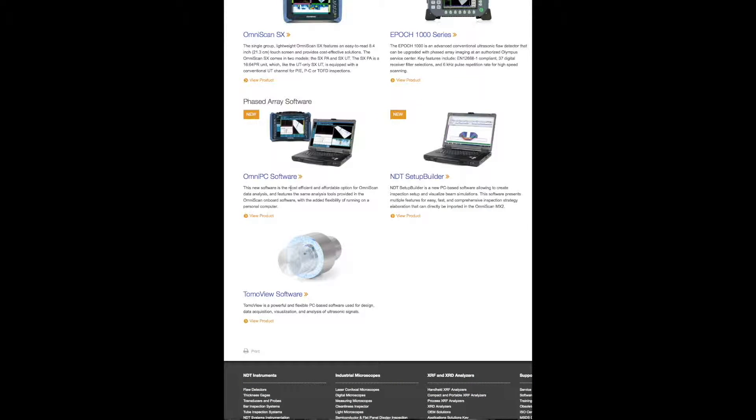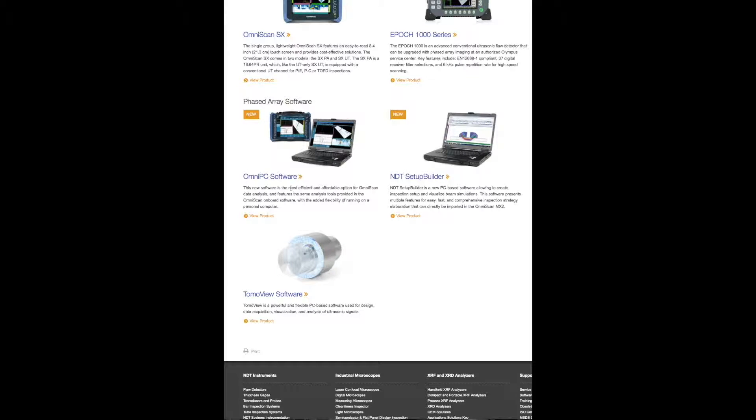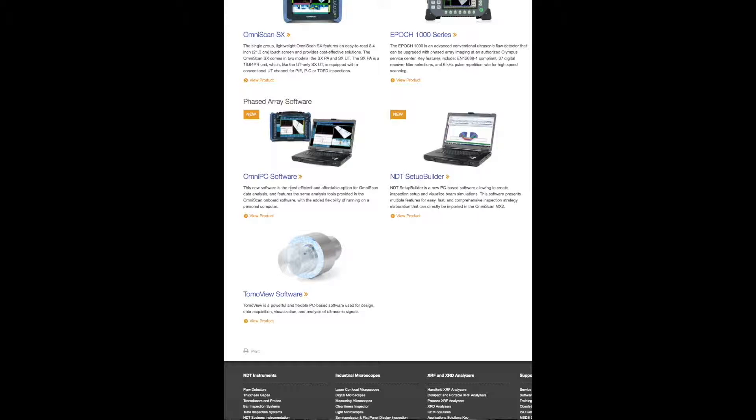Some of the software that Olympus has are Omni PC, NDT Setup Builder, and TomoView. Omni PC is a Windows-based software that is used to build setups and change the settings, so basically it mirrors your OmniScan onto your PC. NDT Setup Builder is again a Windows-based software. It is used to build your setups or your focal laws, your inspection plans, scan plans, and then you can import those into OmniScan.